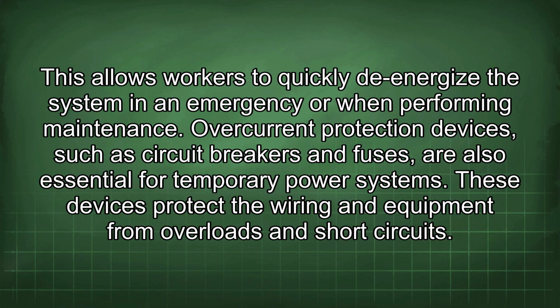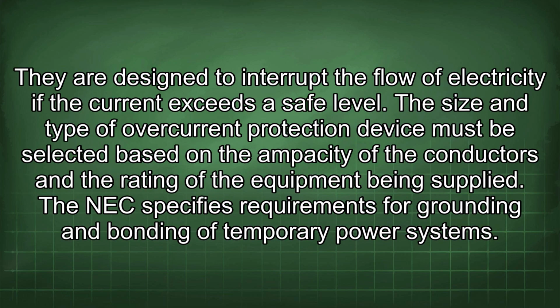Overcurrent protection devices, such as circuit breakers and fuses, are also essential for temporary power systems. These devices protect the wiring and equipment from overloads and short circuits. They are designed to interrupt the flow of electricity if the current exceeds a safe level. The size and type of overcurrent protection device must be selected based on the ampacity of the conductors and the rating of the equipment being supplied.